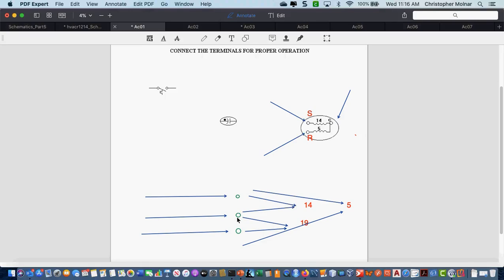So then I have to look for where my next highest resistance reading is, which is my 14. I can tell you right now that this terminal right there is my start, because my next highest resistance reading is start to common. If I know that this terminal is start, and I've already ruled out that this terminal is common, I can tell you right now that that terminal is run, and that is C.